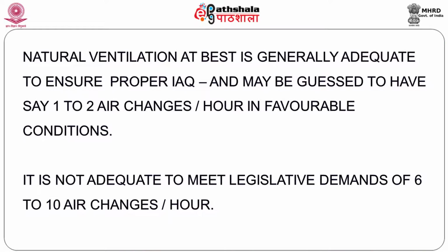It may not be useful for control of environment to make it habitable for a person, not in the tropics, but equipment definitely can be very well served by natural ventilation. This is a repeat of what I just mentioned, that natural ventilation can give you perhaps 1 or 2 air changes per hour, which is absolutely enough to maintain good oxygen levels and perhaps indoor air quality, but perhaps not enough for thermal comfort, for which you might have to look at higher levels.